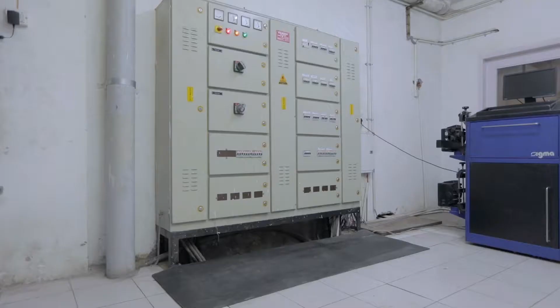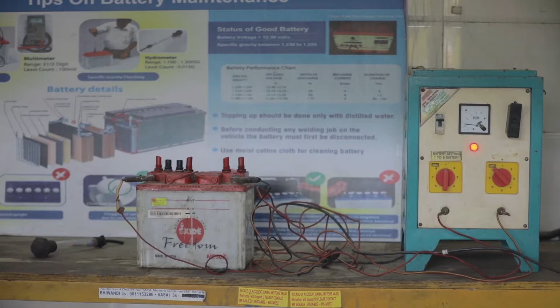Electrical safety. Battery charging. The charging of lead-acid batteries can be hazardous due to the hydrogen gas generated during charging process and the sulfuric acid in the battery. The room should be well ventilated to prevent any explosion. Signs such as no flame, no smoking or avoid use of any source of ignition should be displayed outside the room.